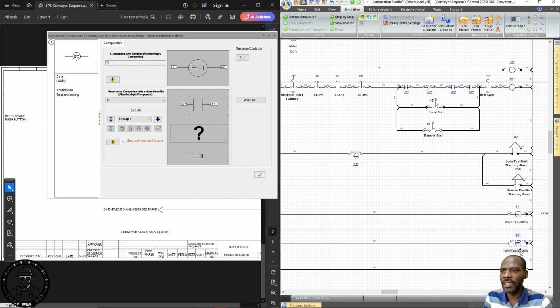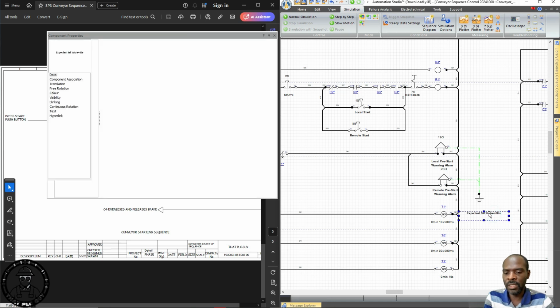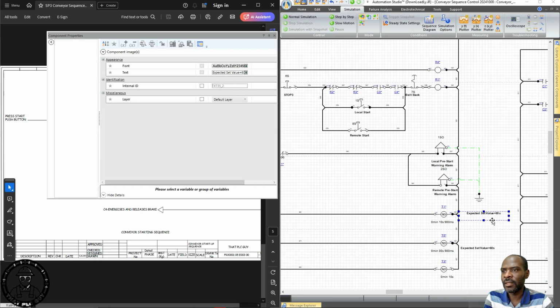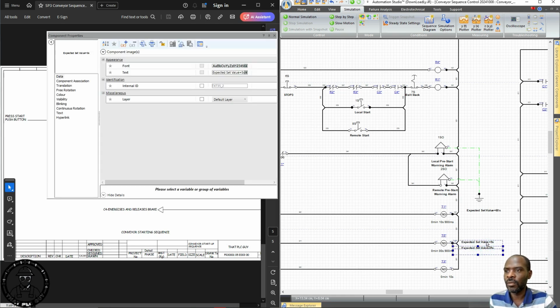So we've set 900 milliseconds for T5, and the expected outcome is that we should be able to get 5 seconds out of this setting. The actual expected actuation point is 5 seconds, in as much as we have set 900 milliseconds, because of the reasons we earlier observed.